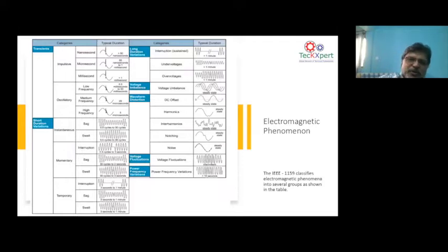Now you go into the other area of voltage distortion. Here we call short duration distortions. When you say short duration variation or distortion, it could be a sudden spike or a sudden sag in the voltage. So where does the sag in the voltage come from? Imagine a short circuit takes place somewhere in the BESCOM network, or let's say a branch of a tree falls over the line. Suddenly there is a temporary short, and when the short circuit takes place, there is a voltage sag.